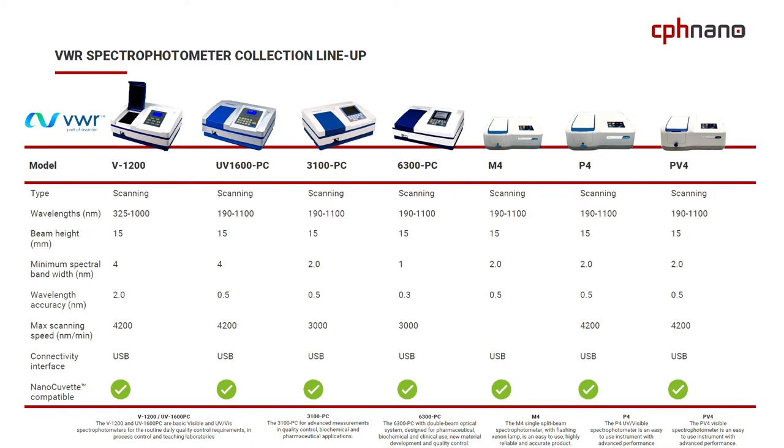On one hand we have the V-1200 instrumentation — that's the one I'm standing in front of right here. It's an entry-level instrumentation and it's not full wavelength. But the rest of the instrumentation — the UV1600PC, the 3100PC, the 6300PC, as well as the M4, the P4, and the PV4 — are all full wavelength from 190 nanometers all the way up to 1100 nanometers, which is basically the full range you can get out of a silicon diode-based UV spectrophotometer.